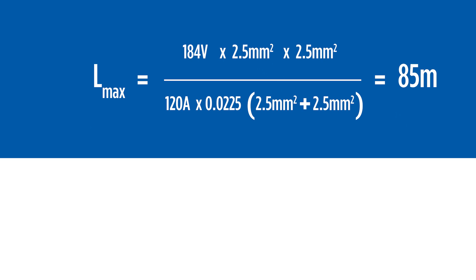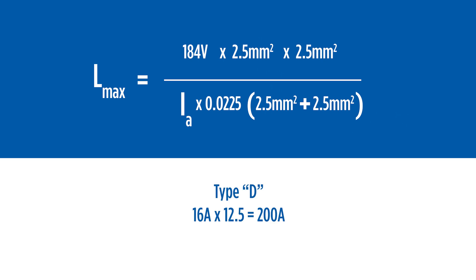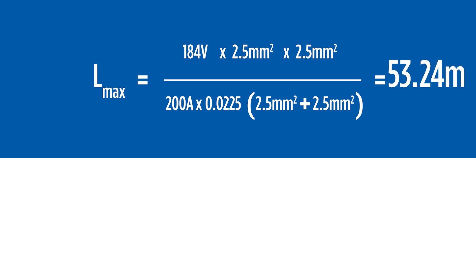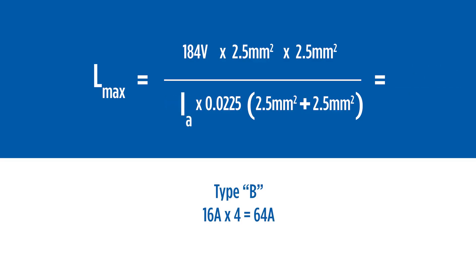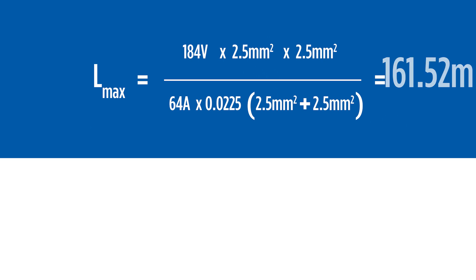A circuit length greater than this may result in fault loop impedance not being satisfied. Swapping the C-type breaker for a D-type breaker of the same rated current results in a maximum length of 53.24 metres, as the D-type breaker requires a higher fault current for instantaneous operation. Substituting a B-type breaker in the circuit will significantly increase the maximum circuit length, due to the lower value of fault current required for instantaneous operation.